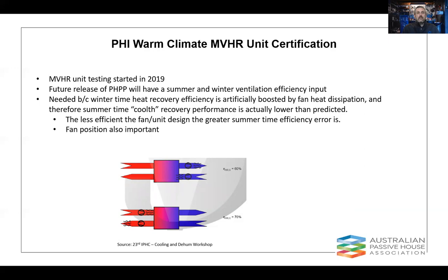What has been fairly evident from early on is that summertime operation is slightly different to wintertime operation in terms of efficiency. And the main thing that's contributing to that effect is actually heat dissipation from fans. And so if we have a look at this diagram at the bottom here, we can see that those round circles there are the fans in the airstream. And we find that under all conditions, they're actually going to contribute some heat to the airstream. So anytime we have inefficiencies in fans or motors, and that's always the case, not all electrical power is converted into mechanical power or airflow or fluid movement, we're going to get some heat dissipation.